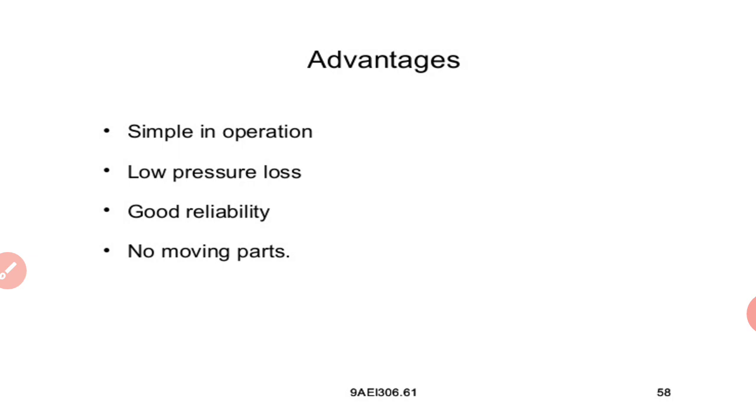Some characteristics of these: Venturi tubes are available in sizes from 100 mm to 813 mm with a flow coefficient of 0.984 for all diameter ratios. Its accuracy ranges from plus or minus 1/4% to plus or minus 3%. It is less affected by decreasing Reynolds number. So if there is a decrease in Reynolds number, it is less affected.